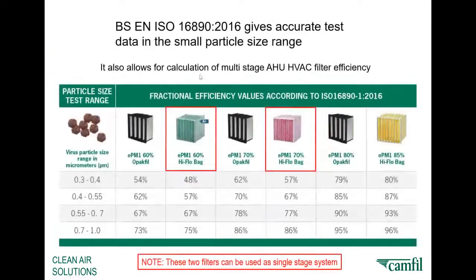So air filtration can be selected for very high efficiencies, and it can also be multi-staged. You can see here a selection of filters, and indeed they show very high efficiencies in the small particle size range, below 1 micron going down to 0.3. As you go up the range, the particle removal efficiencies are very high in these particular filters. These two are landmark filters because they can be used as single stage filters as well as multi-stage, which is a very good idea because then you can minimize the energy consumption. You don't need pre-filters with these filters. They can be used, or in fact they can be used as pre-filters.